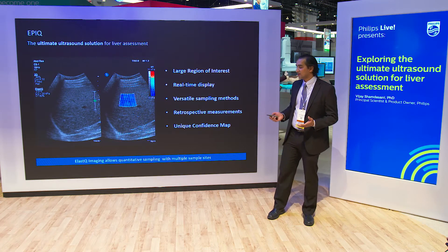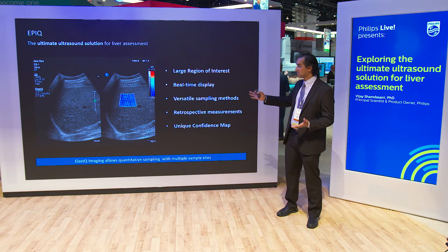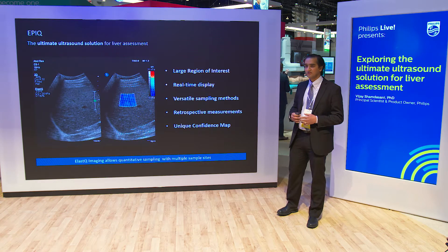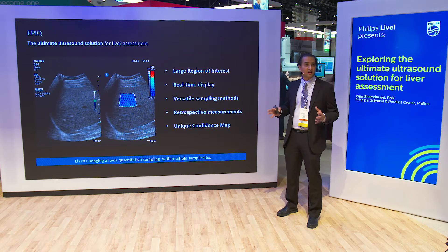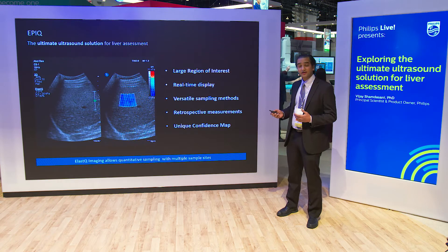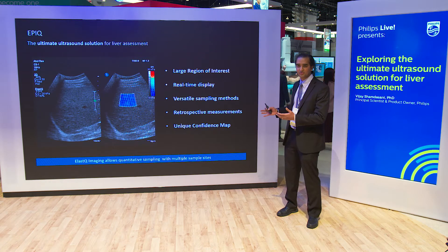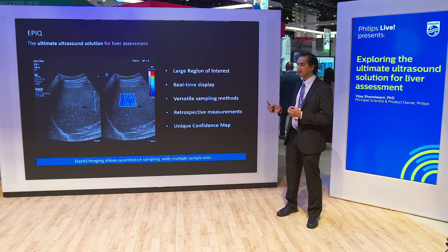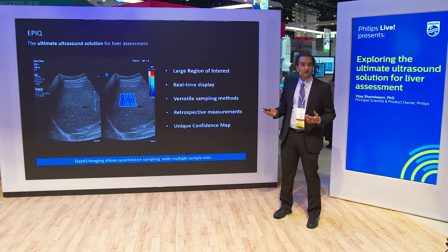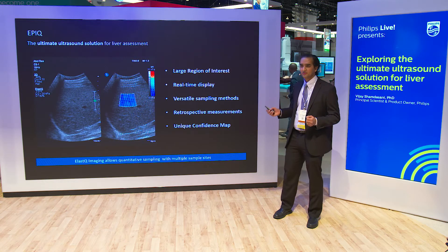Among the advantages of ElastQ Imaging: it offers a large region of interest, real-time imaging, and versatile sampling techniques that allow sampling of a large region of the liver. You can do retrospective measurements — collecting loops of information, reviewing them, and extracting stiffness numbers tied to fibrosis. A unique confidence map indicates which regions inside the liver have the strongest shear wave signal that can be used to quantify liver stiffness.